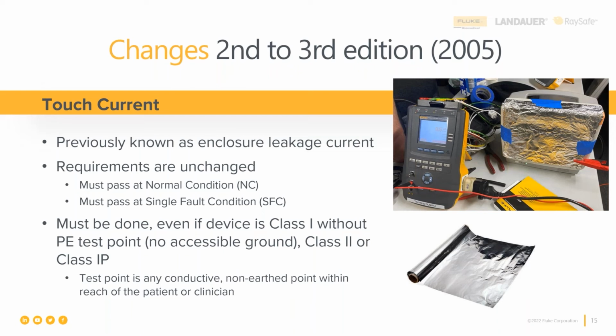So how do you do that? Take about a 4-inch square of aluminum foil, 2 or 3 thicknesses so it doesn't tear. You wrap the edges together, then put it in really good close contact with the touchable surface of the medical device and tape it down. You can see in the picture here we have done just that on this particular patient monitor. Then we connect our measurement lead to the aluminum foil. Now we are able to see on our electrical safety analyzer exactly how much leakage current is available when the patient touches it or the clinician touches it and touches the patient.